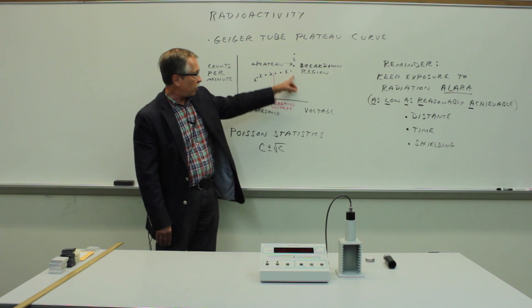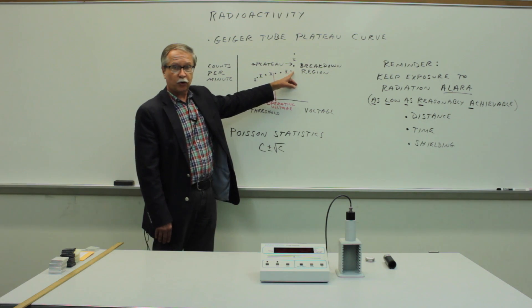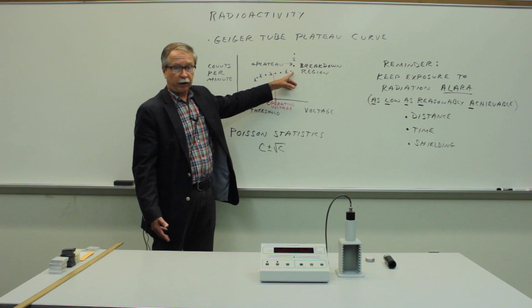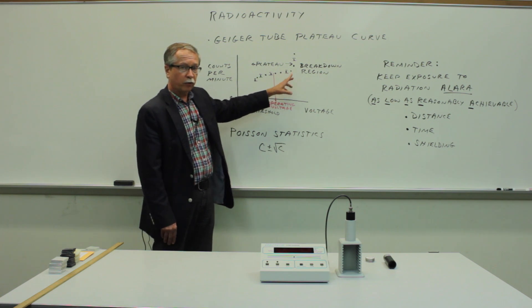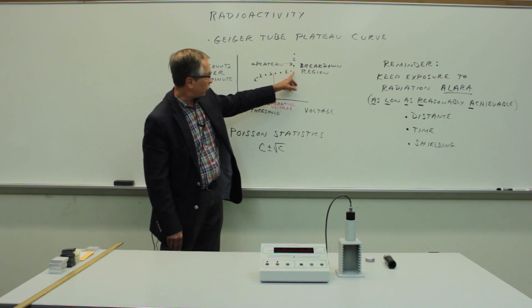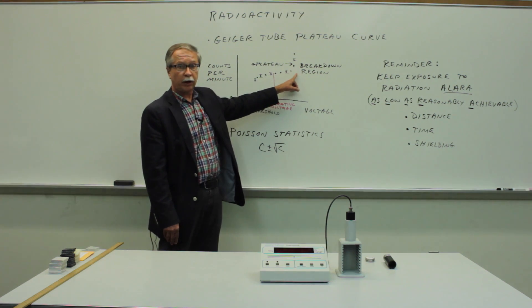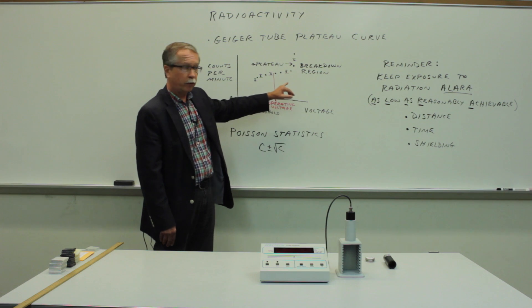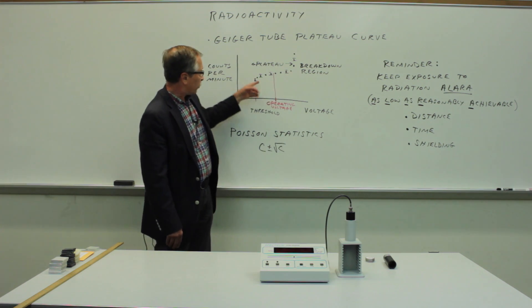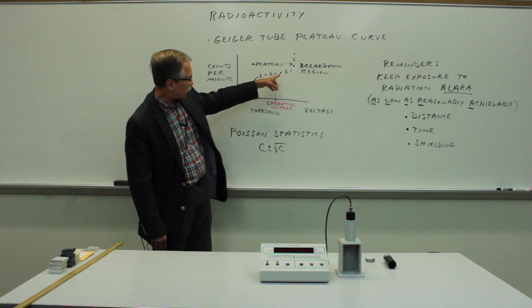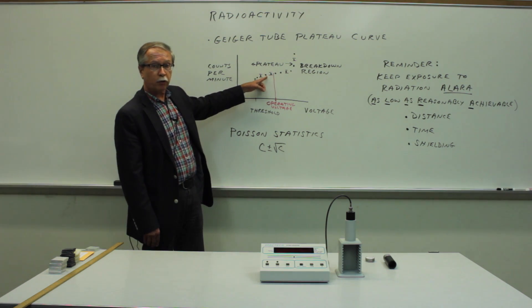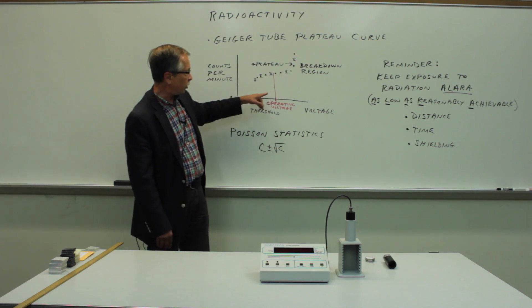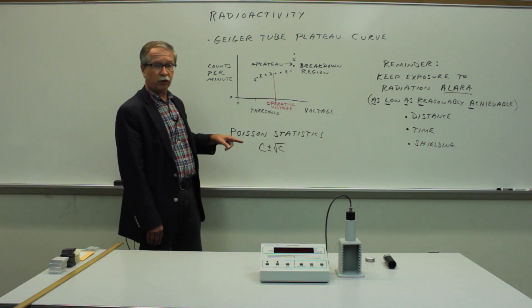Then you'll hit a voltage that will cause the tube to spontaneously ionize and that's not particularly good for the instrumentation. So you can measure a few points into the so-called breakdown region but don't go very far into it. That's really not good for the counter. So what we're looking for is the midpoint of this plateau region, the part that is slowly increasing and we'll choose that as the operating voltage.